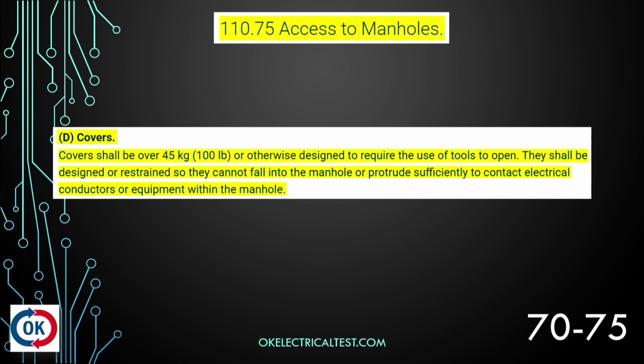And that cover needs to weigh at least how much? It says over 100 pounds. I think on the test, most often they ask what's the minimum weight for a manhole cover, and the highest choice is 100 pounds. Now, that's not technically correct, but it's the only one that makes sense. They're trying to get to that 100 pounds. But really what the code says is it needs to be over 100 pounds. How much over? I don't know. An ounce, right? Just over 100 pounds.